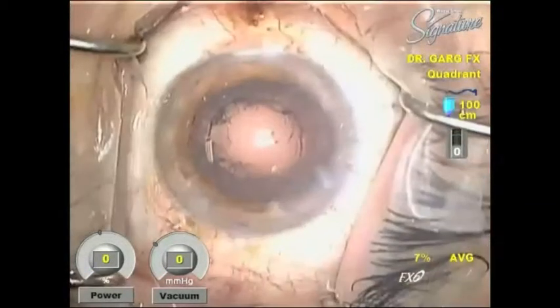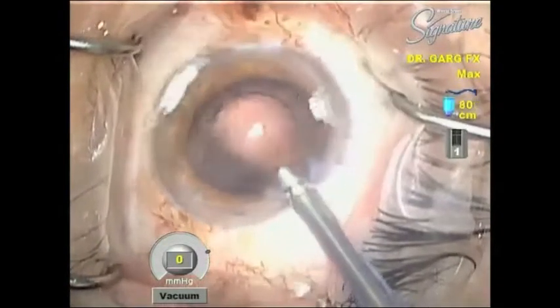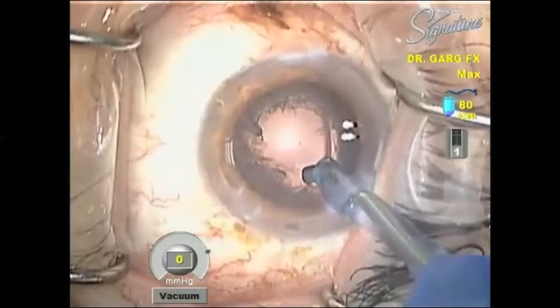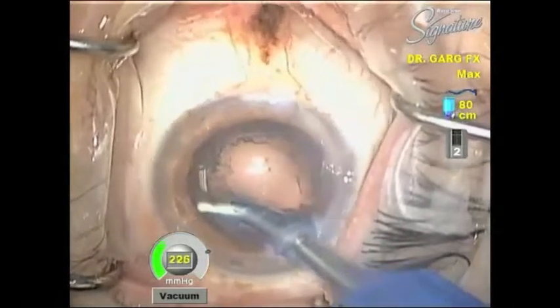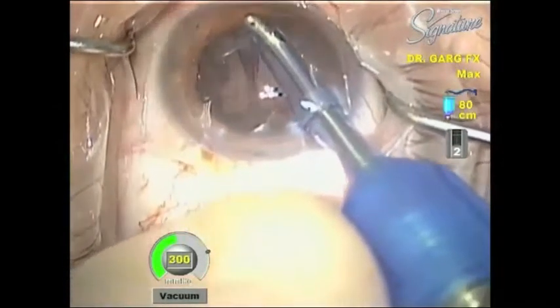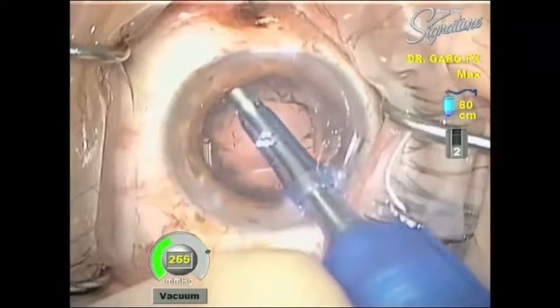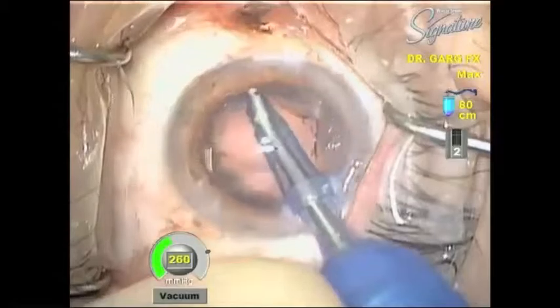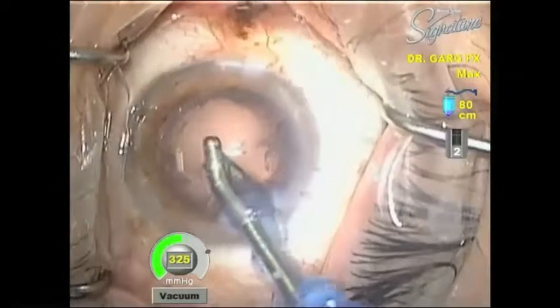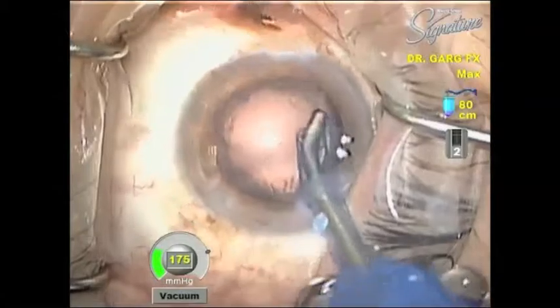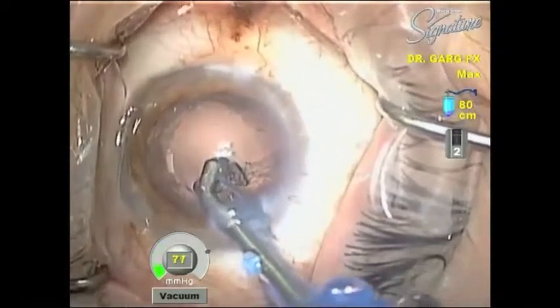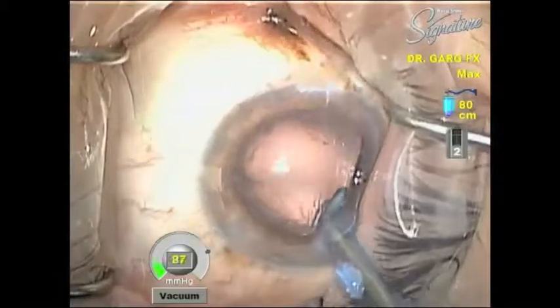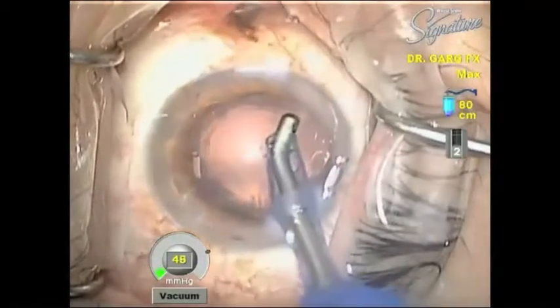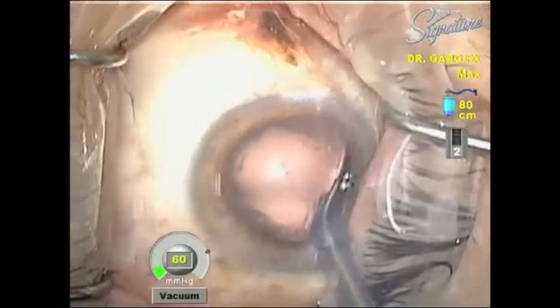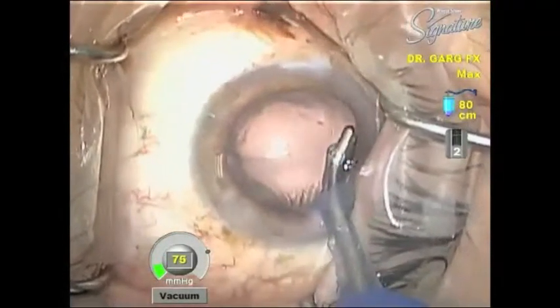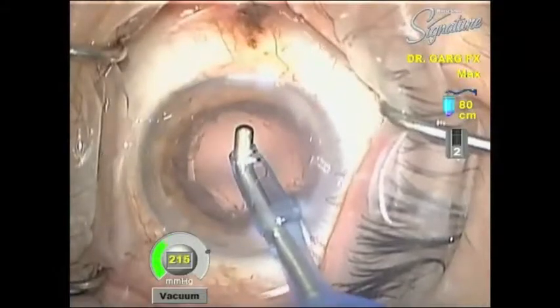Now, with respect to IA, again, using the Venturi pump is efficient because you don't have to go fishing for a lot of the cortical material. The other thing is you don't have to have an occluded tip in order to generate vacuum. And so the removal is more efficient. I find it's most efficient when actually removing the OVD, because you do not have to go behind the IOL to remove any OVD, thereby being a little more predictable in having less pressure spikes day one.